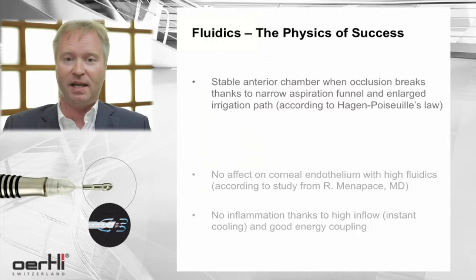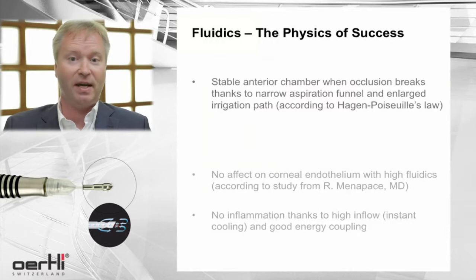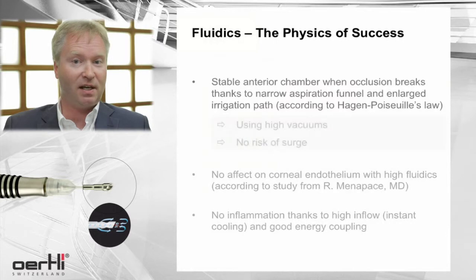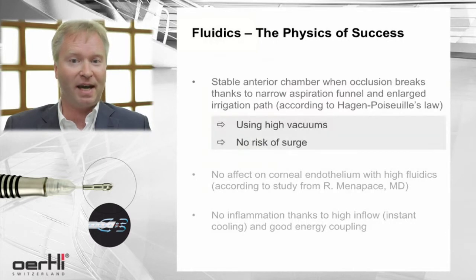On the other hand, active aspiration is not affected by the narrow aspiration funnel. So this gives you two advantages: you can apply high vacuum rates, and you have the safety of not being at risk of surge.